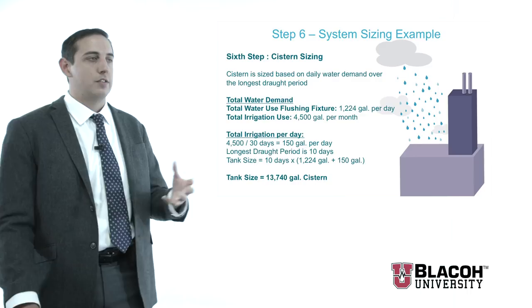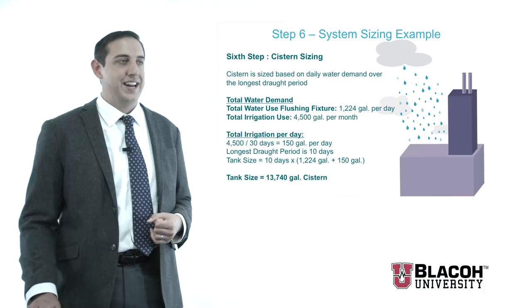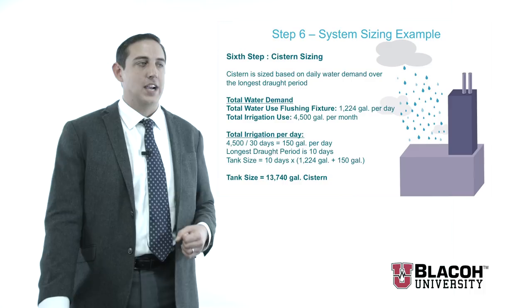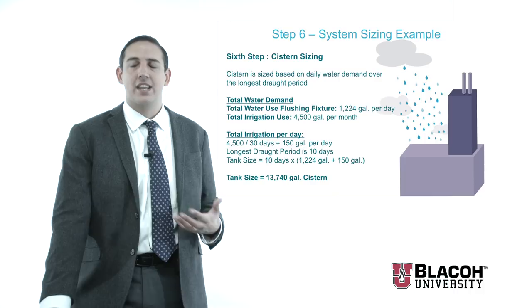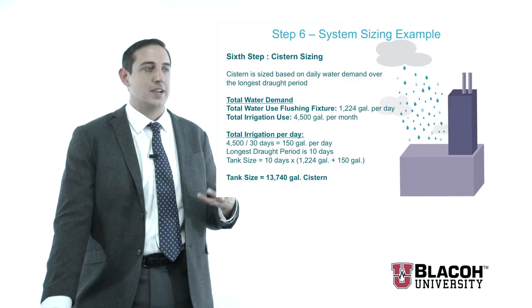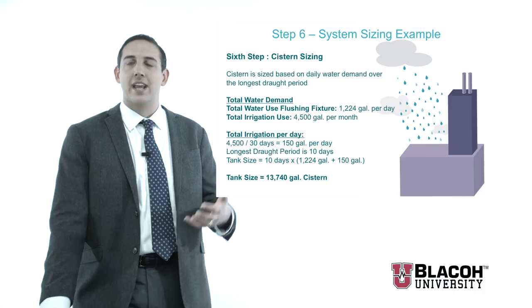Looking at my cistern sizing, I'm going to size it based on my longest drought period, which in this area is about 10 days. Looking at my flushing fixtures of 1,224 gallons per day and my total irrigated area of 4,500 gallons per month — dividing that out, I need about 150 gallons per day for irrigation. Adding that to my 1,224 gallons times my 10 days, I need about a 13,740-gallon cistern, which makes sense. I'm going to get about four precipitation events per month, collecting about 15,000 gallons each event to fill up my 45,000 gallons of collectible rainwater.